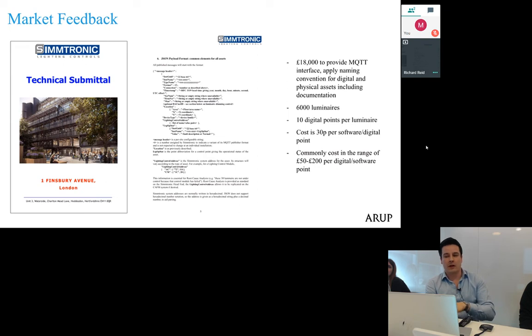They have also, in conjunction with Francesco over the last couple of years, first developed a BACnet server so that, because they are a proprietary system, we could get data from their system in a common language. Next step, Francesco convinced them to develop an MQTT server, so now we no longer need the gateway, because they're exposing MQTT right down at the subsystem level. They have adhered to our naming convention and applied it to this project.